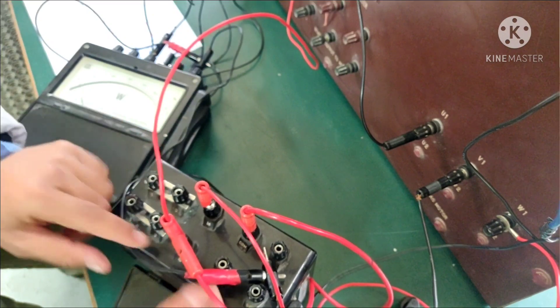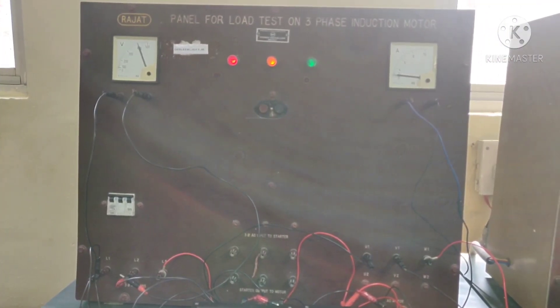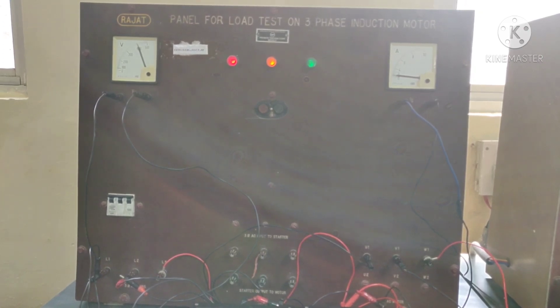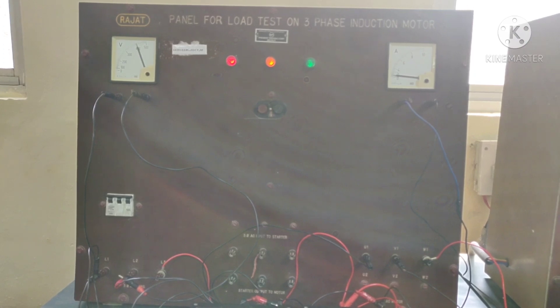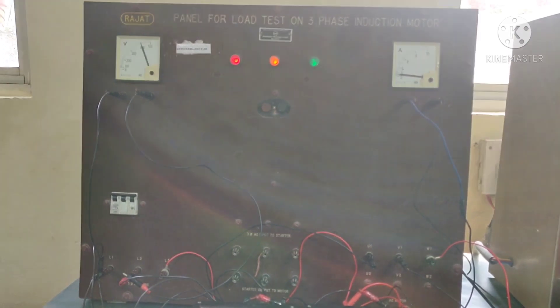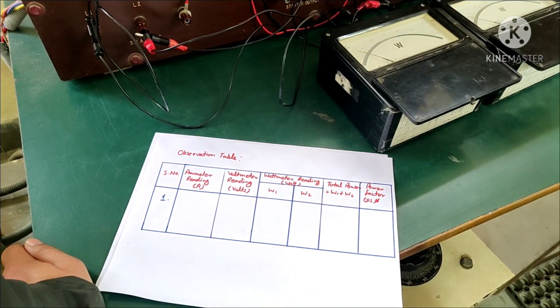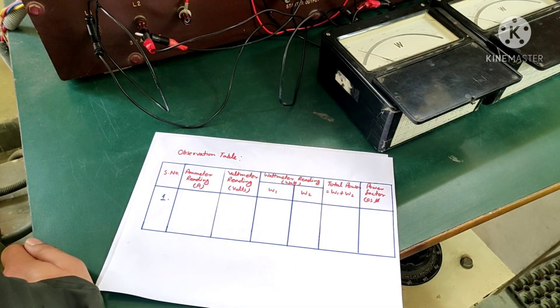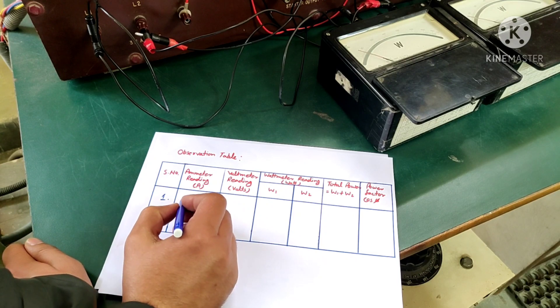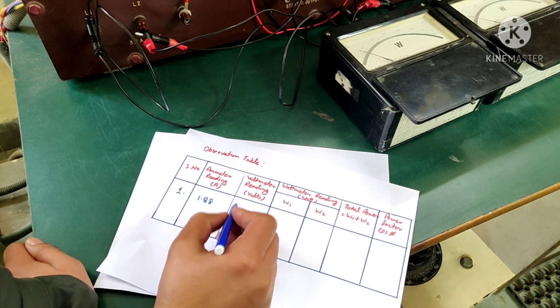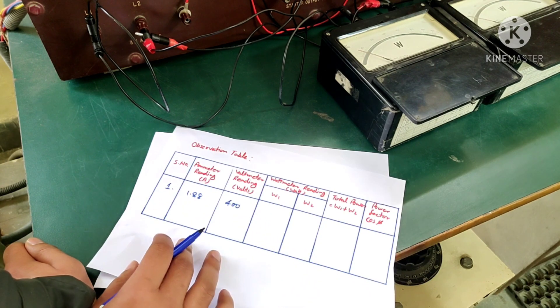So before taking the reading of the wattmeter, let us check out the voltage and current. So we have provided this panel, or you can say the induction motor, a voltage of 400 volts approximately, and the current drawn comes out to be 1.88. Accordingly, let us now fill our first two columns of the observation table. Ammeter reading is 1.88 and voltmeter reading is 400 volts.